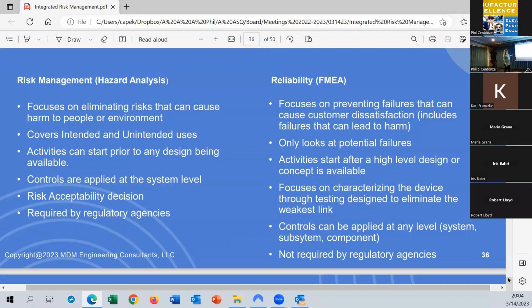In the hazard analysis, controls are applied at the system level. In an FMEA, you can apply controls at any level of the system. The hazard analysis is where we make risk acceptability decisions. In the regulatory environment, it's important to have risk acceptability in one place. I've seen manufacturers that make risk acceptability decisions in different FMEAs. Now you're trying to put it all together and ask, well, what's this risk really?